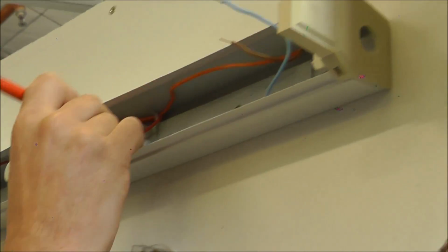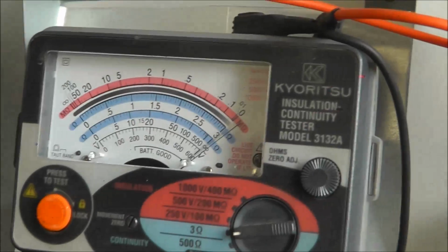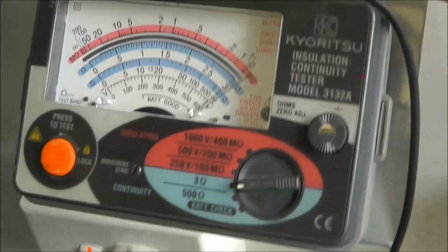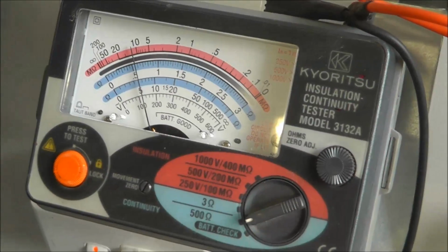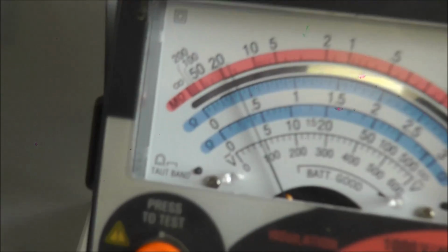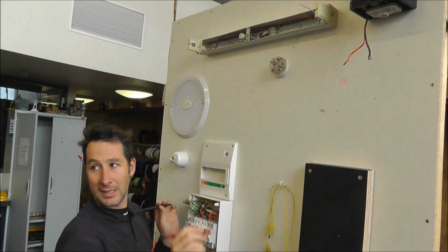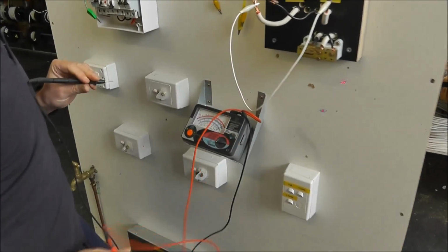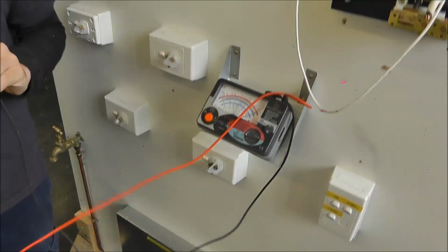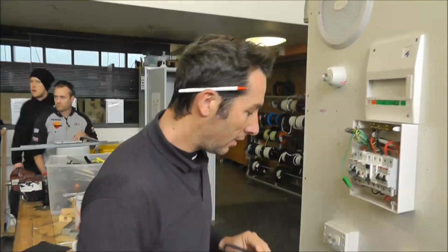Now, it hasn't moved there one bit, Dobbo. So flick that scale over to 500 for me. Oh, imagine that. Imagine if you forgot to do that. There's 4 ohms on that fluoro. Obviously very important to flick the scale. Yes? Yep. Back to 3 ohms. Someone's writing these down in the spots, I imagine.